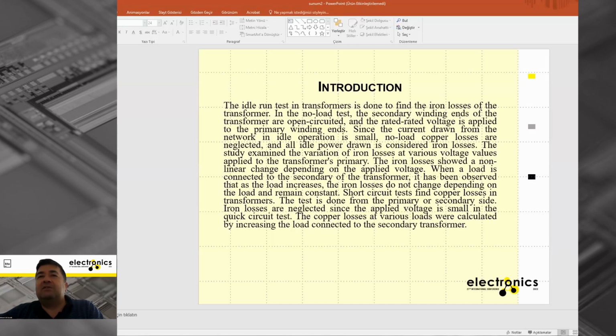The study examined the variation of the iron losses at various voltages applied to the transformer primary winding. The iron losses showed a nonlinear characteristic with the applied voltage. When a load is connected to the secondary winding of the transformer, it has been observed that as the load increases, the iron losses do not change depending on the load and remain constant.